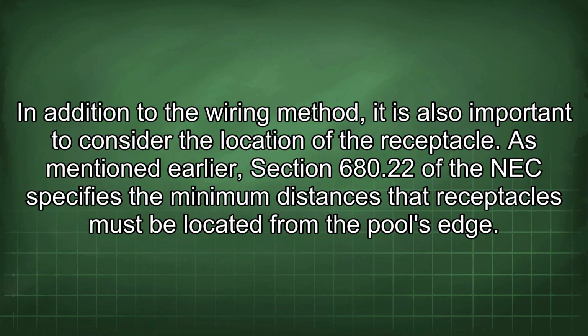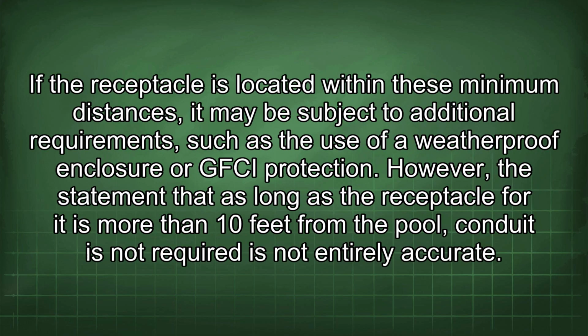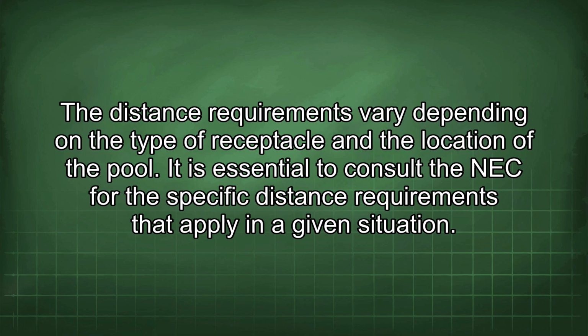In addition to the wiring method, it is also important to consider the location of the receptacle. As mentioned earlier, Section 680.22 of the NEC specifies the minimum distances that receptacles must be located from the pool's edge. If the receptacle is located within these minimum distances, it may be subject to additional requirements, such as the use of a weatherproof enclosure or GFCI protection. However, the statement that as long as the receptacle for it is more than 10 feet from the pool, conduit is not required is not entirely accurate. The distance requirements vary depending on the type of receptacle and the location of the pool. It is essential to consult the NEC for the specific distance requirements that apply in a given situation.